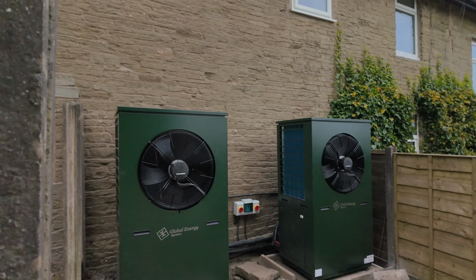Now, it was heated with a huge oil boiler in the basement, and then they had a massive oil tank, which is where we've installed the heat pumps. So we've got two heat pumps that are, I'm trying to think exactly what the heat loss is. Heat loss is 26 kilowatts. The heat pumps themselves can do 28 kilowatts, actually a touch more than that, and that's with defrost as well. They can deliver that like true heat output. We've cascaded them together here.